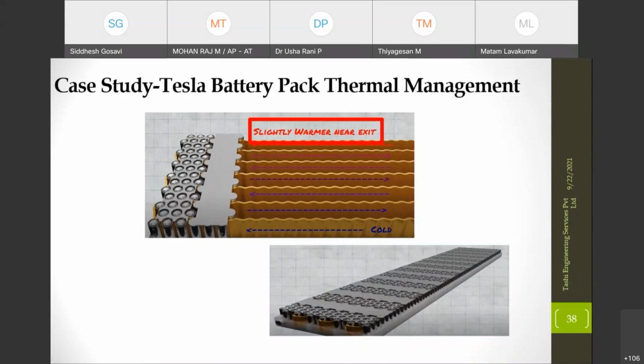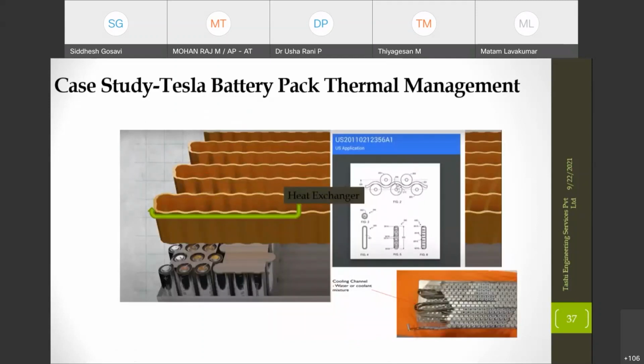The current design uses flow rates and channeling such that temperature non-uniformity is minimized. If it's a single channel pathway, with fluid coming in and going like a snake, the temperature non-uniformity will be higher. So one objective is to have parallel pathways, with multiple inlets and multiple outlets instead of just one, so temperature non-uniformity is as minimum as possible.